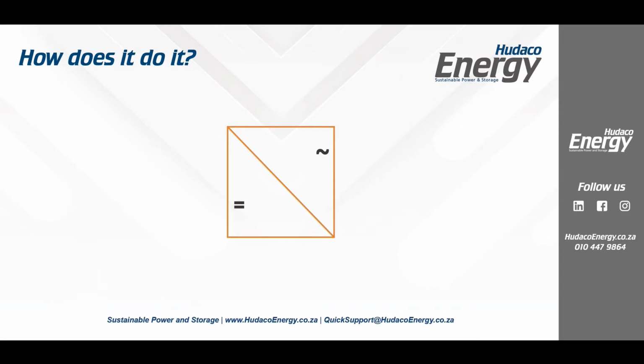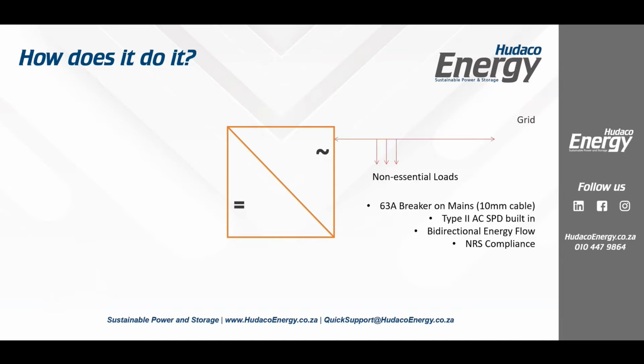So that's the inverter. Can everyone see my little dot? Here we've got the AC side, our sine wave, and here we've got the DC side of the inverter. We've got 4 connection points, excluding the comms. The first connection point is labeled grid port. The grid port is where we connect the inverter to the home's network, your existing DB, and also it's where the non-essential loads would be positioned before we connect to the inverter.